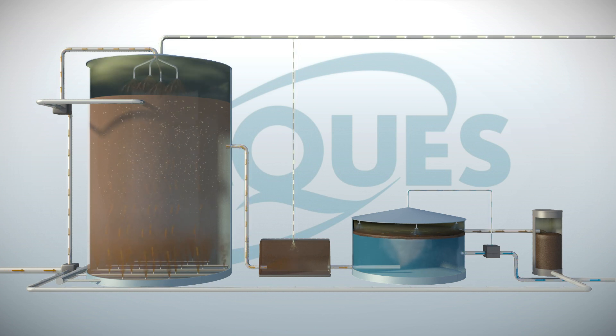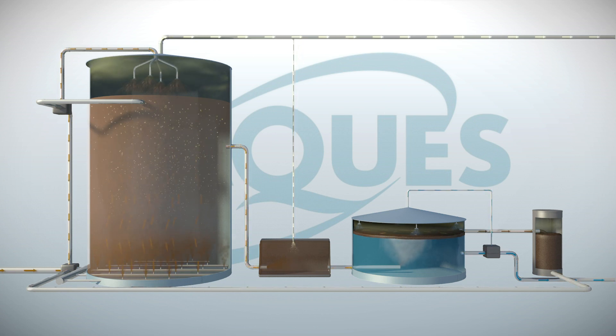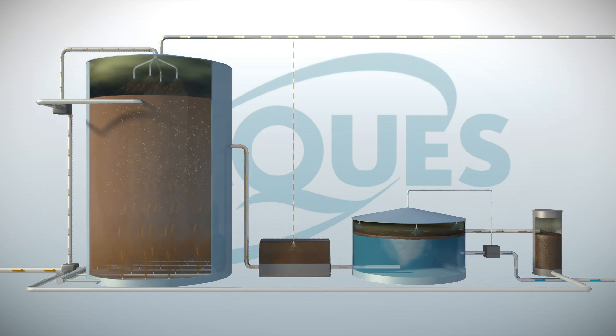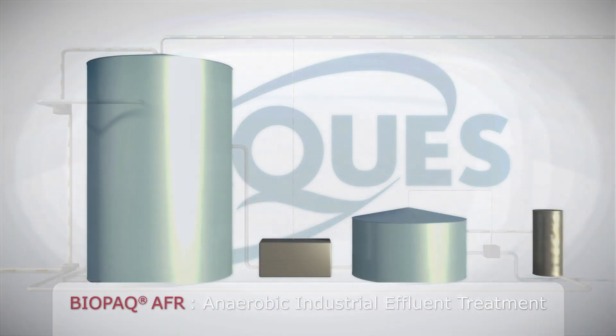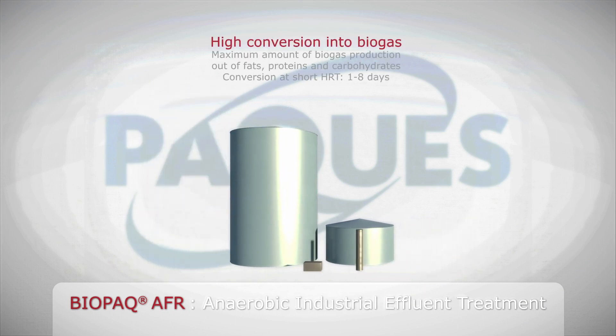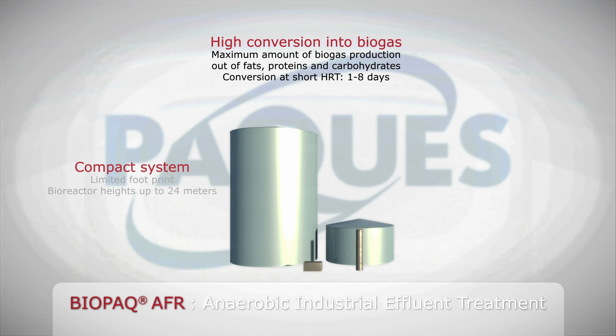The BIOPAQ AFR process is applied in a variety of industries such as the dairy industry, food tank cleaning, fish processing and poultry industry. The AFR system maximizes the biogas production from fats, proteins and carbohydrates. Both soluble and insoluble compounds are efficiently converted into biogas at short hydraulic retention times, typically between one to eight days. Due to the efficient retention of biomass, the system is compact and has a limited footprint.